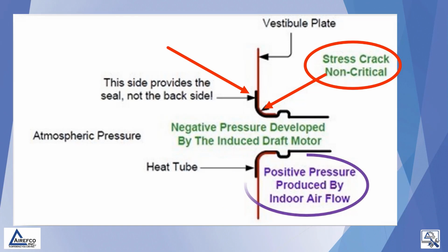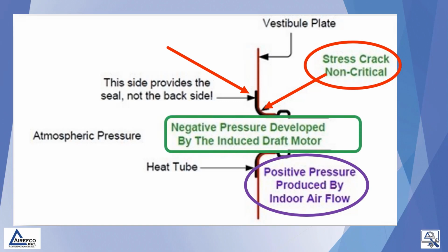Also, because of the positive pressure that is produced by the indoor airflow and the negative pressure that is developed by the induced draft motor, any cracks or holes in the heat exchanger would have air drawn into them and into the heat exchanger and out through the exhaust, not causing a problem for the conditioned space.